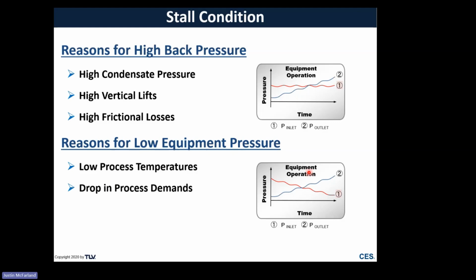Then there's things like drop in process demands. Could be seasonality. So again, hot water heater, think of a university or a hotel, let's say, that is heating a pool. Well, in summertime, they probably don't need to heat it up as much just because you've got more heat from the atmosphere to keep it warm. But then in the wintertime or in the fall, there's more demand for heat. And so they're going to be providing a lot more BTUs during those seasonal times where it's needed. But in the warmer months, there's going to be a drop in BTU requirements, which will need less pressure and inevitably lead to a negative differential pressure scenario.